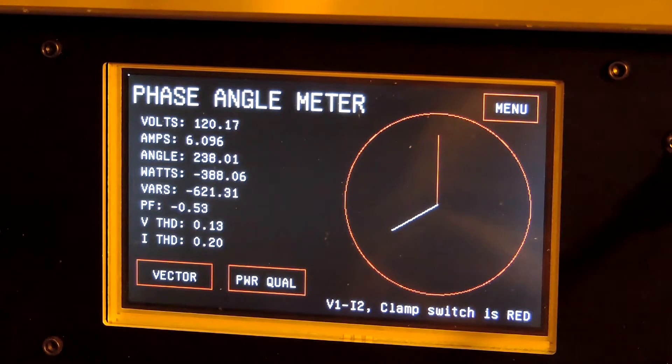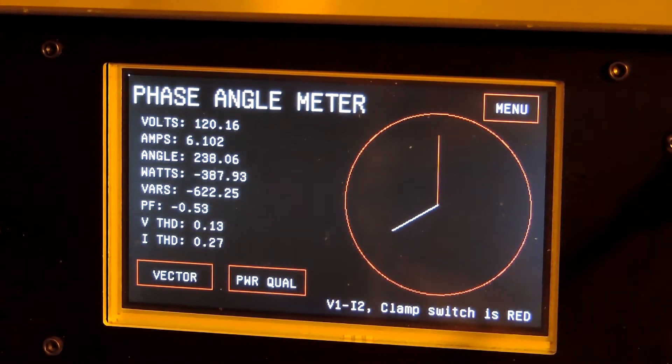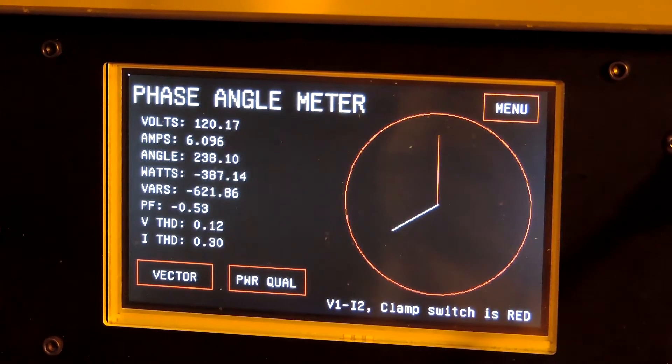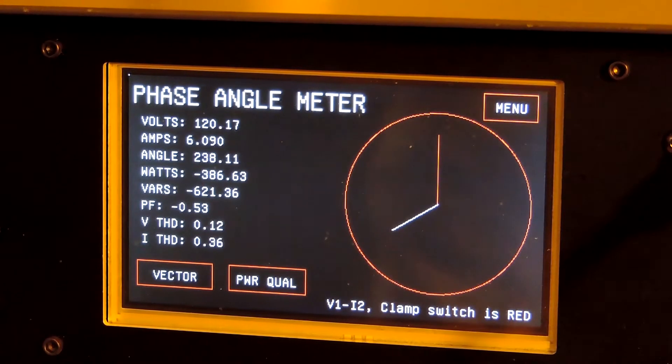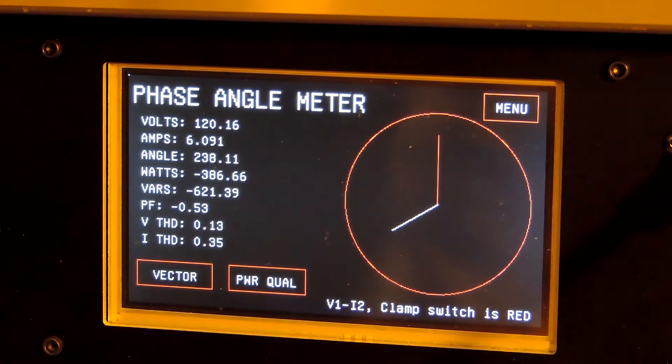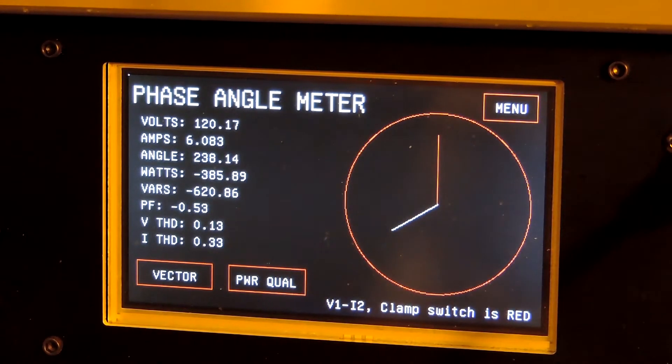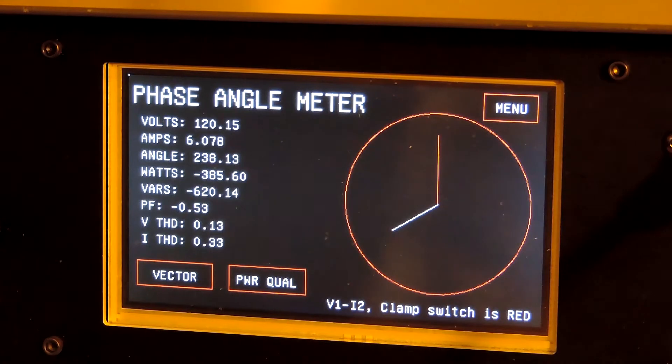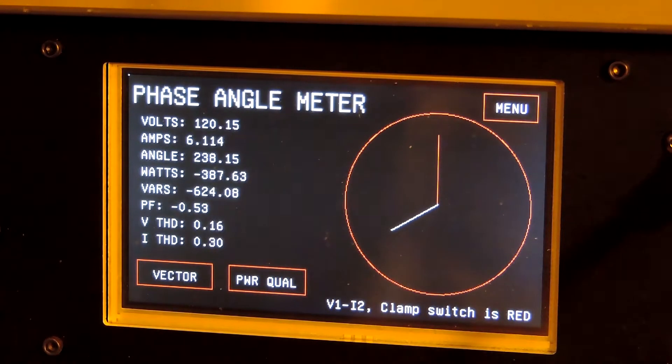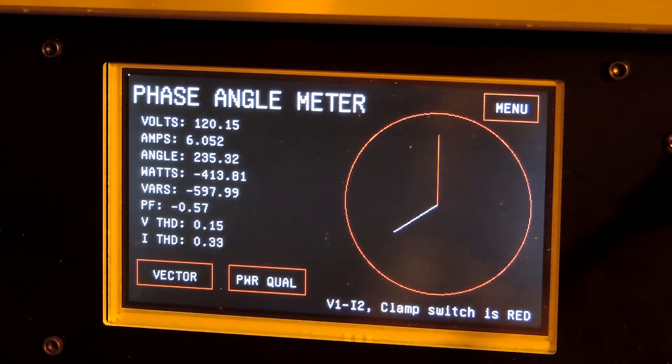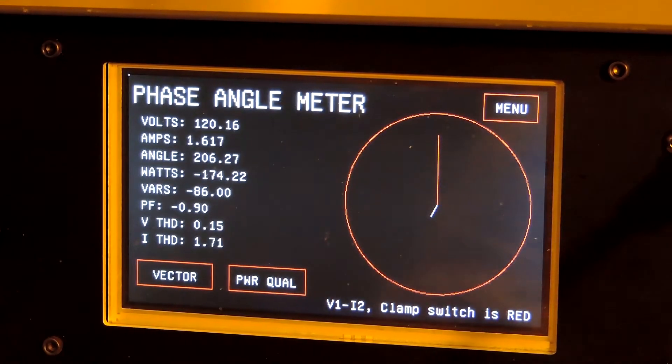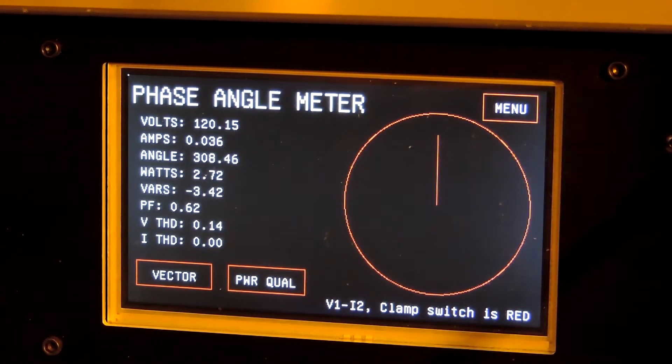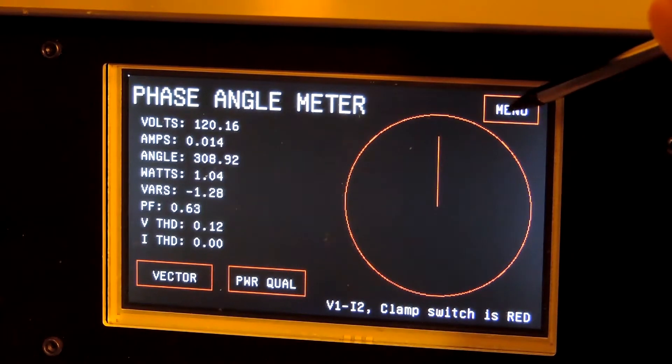As you can see, I have to get it right in the middle of course before it reads right. The clamp-on is about a one and a half percent device. I don't have it precisely located, but you can see that the angle and amplitude is going to be about a two percent thing with the clamp-on. But other than that, it does the same as the hardwire I input.